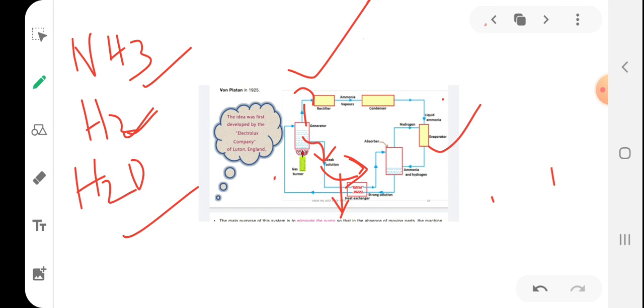Because it transfers heat to the strong solution that is coming from the absorber. So heat is transferred from this weak solution to the strong solution. So the strong solution will be heated even before it reaches the generator. So heat removed by the weak solution is utilized in raising the temperature of the strong solution passing through the heat exchanger. In this way, the absorption is accelerated, right? The absorption is accelerated, and the performance of the system is improved.